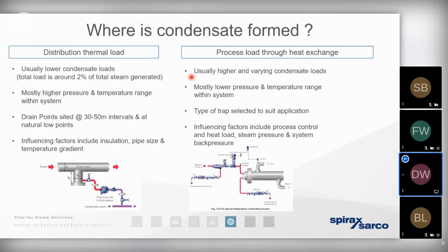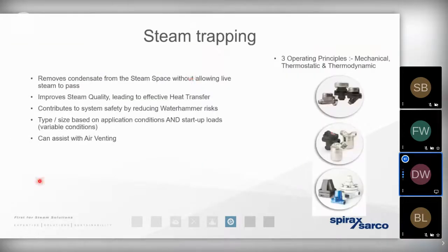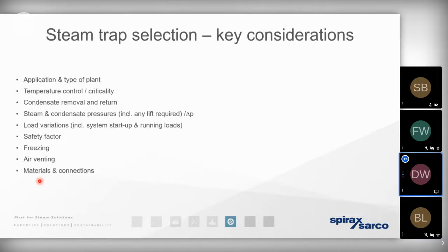So that essentially means that we're going to need to contend with the removal of condensate at different areas, different pressures, temperatures, mass flows. So for that reason, we need to remember there's no such thing as a one-size-fits-all universal steam trap. Each steam trap needs to be sized and selected in accordance with the pressures, temperatures, mass flows, and also the other considerations that the trap is going to be exposed to. For example, is there a lot of temperature variation? Is there going to be a certain amount of air locking, or is it going to be exposed to freezing conditions? All of these considerations are going to point us towards a number of different options for steam trap selection.